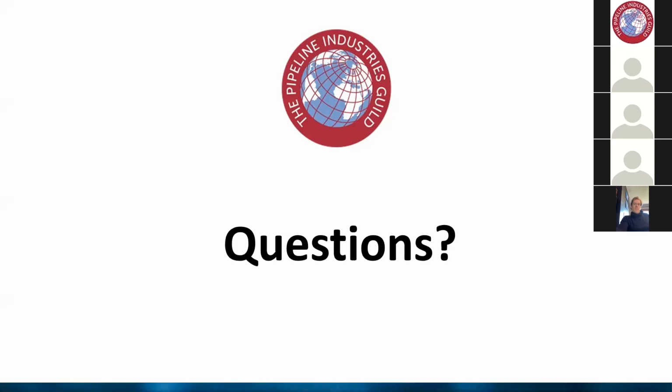That's great. Thanks, Jamie. And just scrolling through, Natalie has said, has there been much innovation in wastewater over the years with the standard processes used, or has it stayed fairly traditional? There have been certain developments. Most of the processes are fairly traditional, but something that the Environment Agency are setting now is consents on phosphorus limits. That's driven some innovation, in particular in how we remove phosphorus from the wastewater treatment process, and we're getting to really low limits on our phosphorus consents.